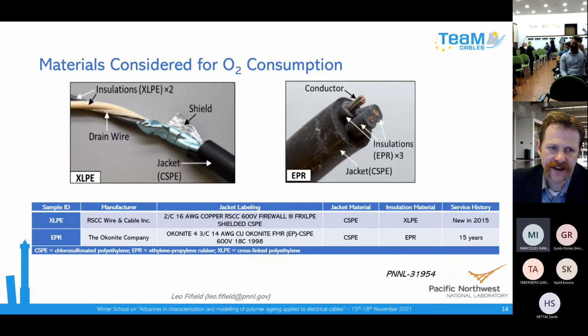Regarding this slide, I understand you have harvested the cable on the right, the EPR, and this EPR has 15 years, but 15 equivalent years, because it's very different. Normally when you harvest a cable you have two problems: first, the difficulty to determine if the jacket is adequate or was destroyed by the harvesting process, and second, normally you harvest the cable in better condition than the worst condition in the plant. The area with higher irradiation and higher temperature is usually very difficult to extract cable from, so you don't know if what you extracted is really the worst or a better condition, and normally the equivalent years are very low compared to the real years of operation of that cable.